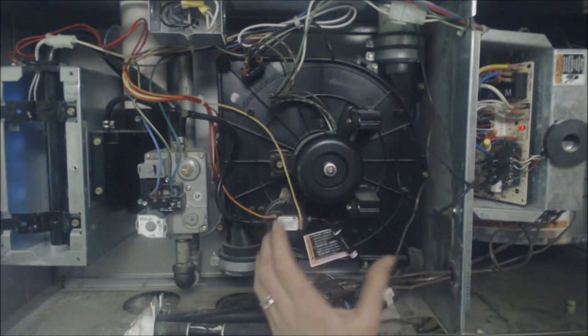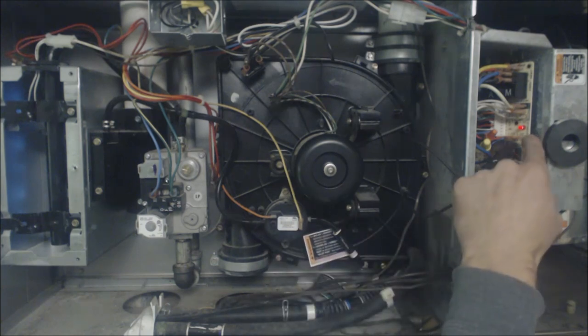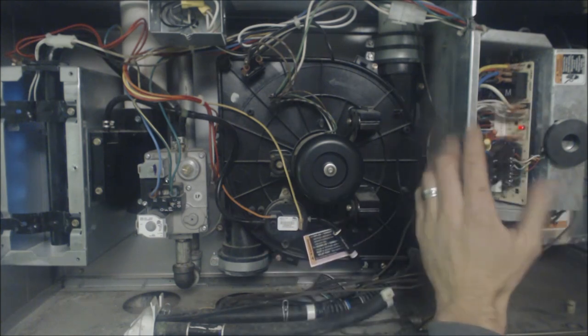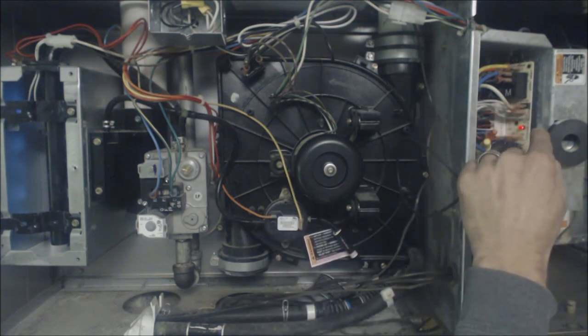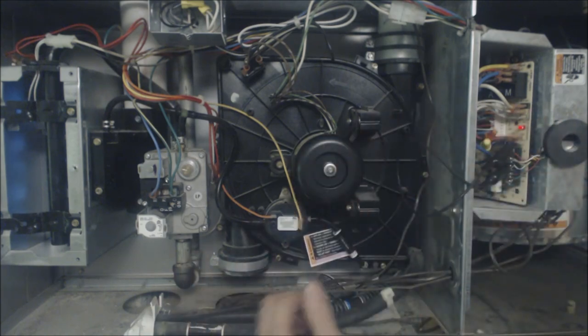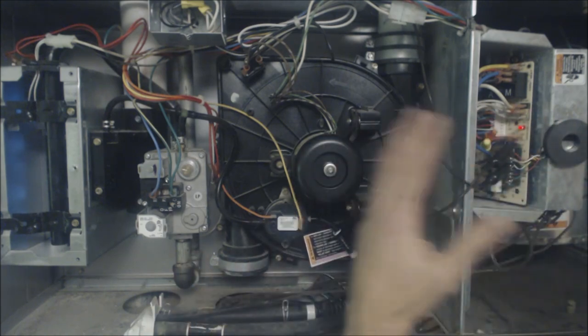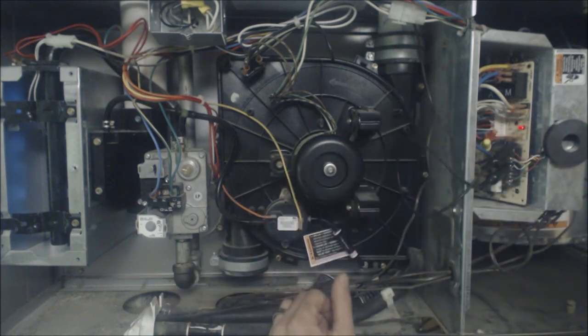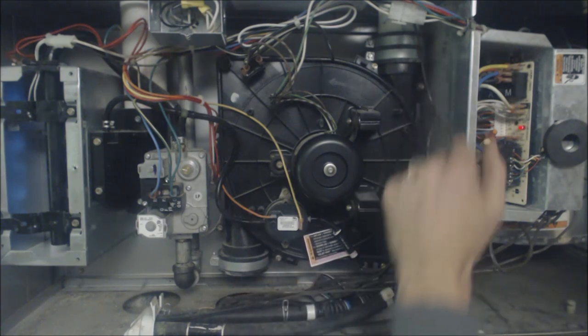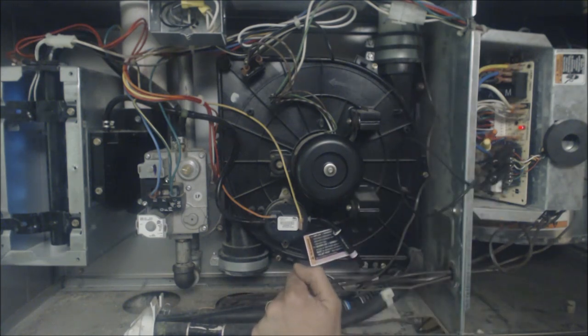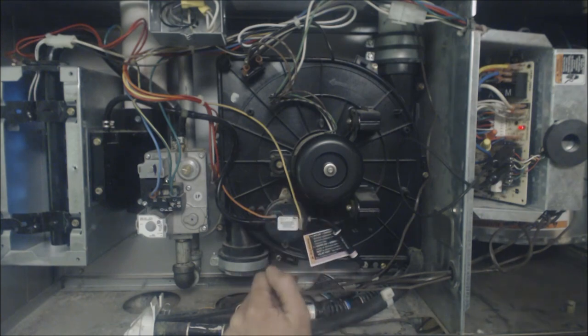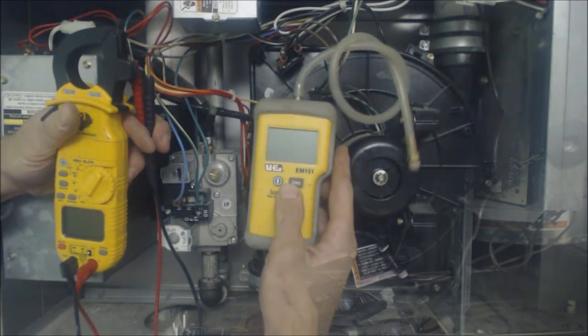And a lot of times the furnace door will tell you the error code that this is reading right here before you take the door off. You read the error code and it gives you, you know, five or six potential things. It just says look for the drain lines, look for the exhaust lines, look for a clogged hose, the pressure switch could be bad, the inducer motor could be bad, stuff like that.